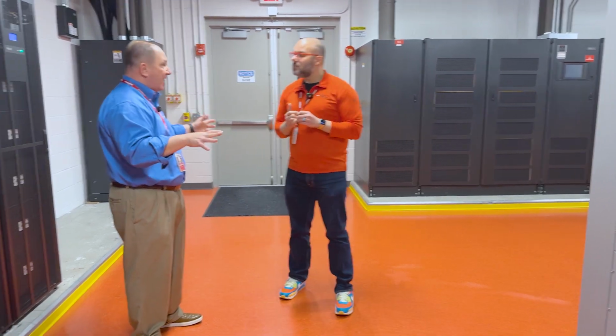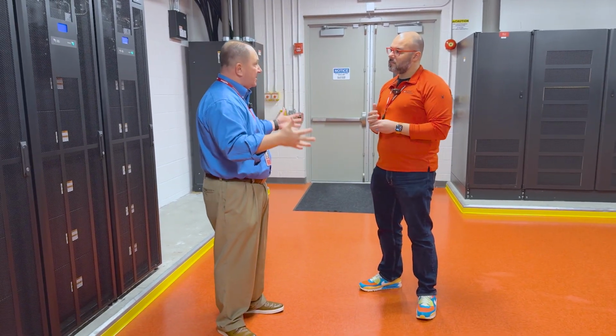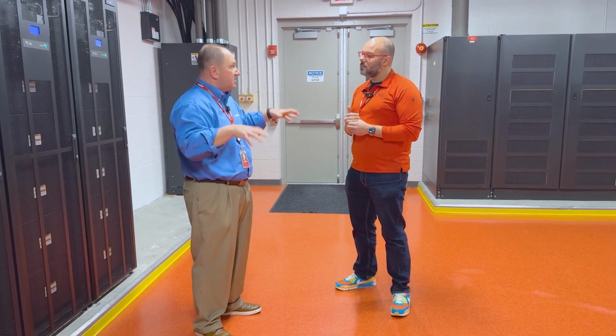Monthly we're doing work inside the data center on the power plant and mechanical systems. Quarterly we do more testing, where we actually test the UPS systems and the backup emergency power plants. We also do maintenance on the UPS system, bringing in all the maintenance providers and manufacturers to service the units, the batteries, and the switchgear to ensure we're getting the proper product and everything works appropriately. It's kind of like keeping up with maintenance on your car - you've got to do the oil changes, get your brakes checked, get your tires checked.